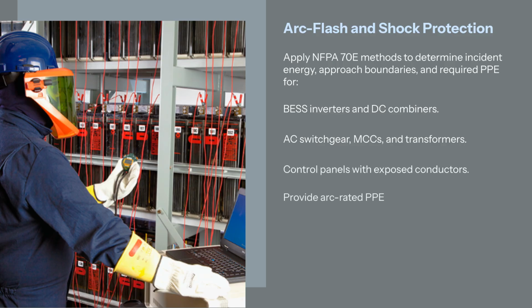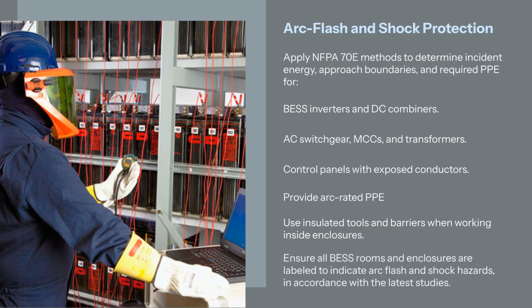Provide arc-rated PPE clothing, face shields or hoods, gloves, and voltage-rated gloves as appropriate. Use approved insulated tools and barriers when working inside enclosures. Ensure all battery energy storage system rooms and enclosures are labeled to indicate arc flash and shock hazards, in accordance with the latest incident energy studies.